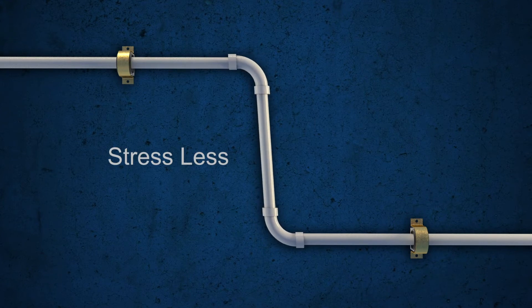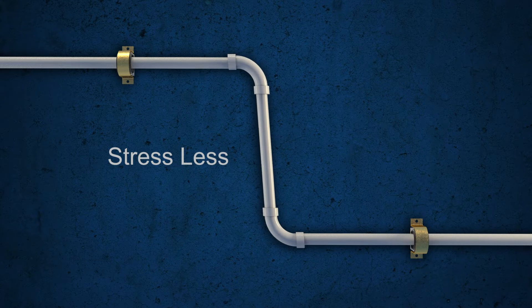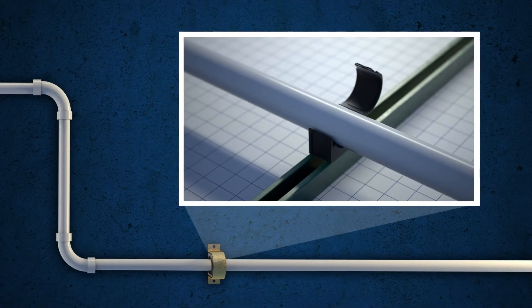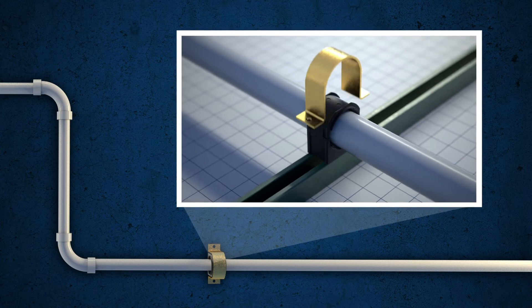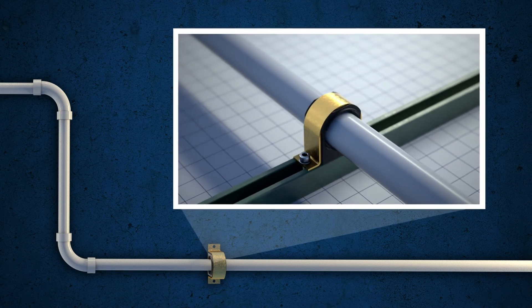The metal bracket provides strength for all operating conditions, including strong seismic events. Due to the engineered gap, the piping system design engineer does not account for load accelerations due to seismic or water hammer events. This makes design of the supporting steel easier.